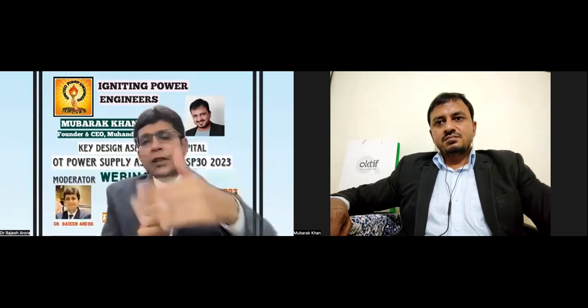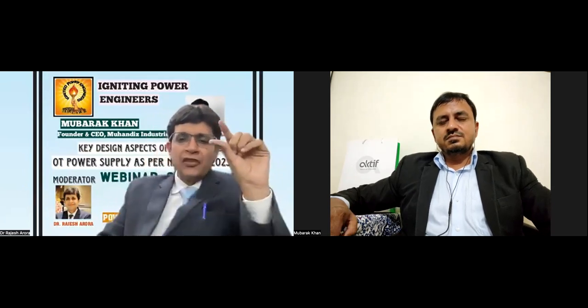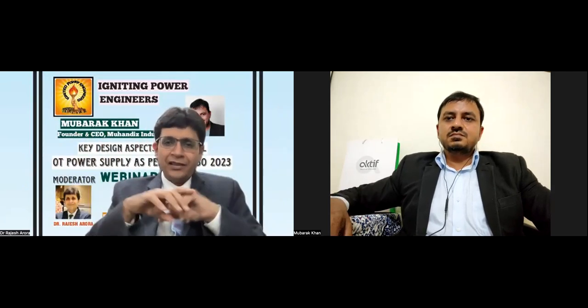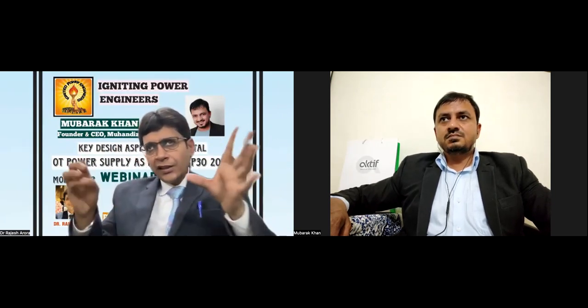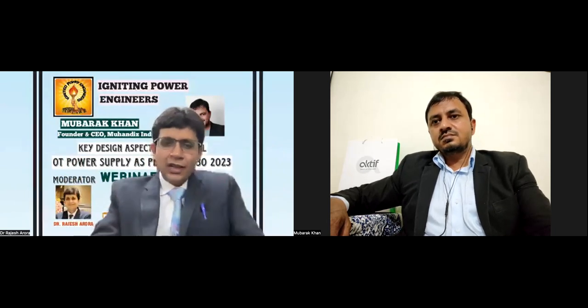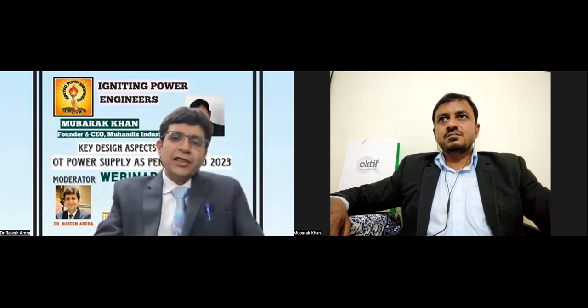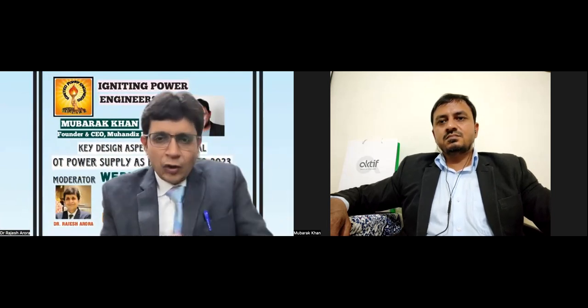If there's some problem with any of the feeders, the insulation monitoring system gives an indication and an alarm. The alarms are in the shape of indication as well as sound, and they will not reset until they are attended by a person working in that hospital. That is the system of working. Your question was about the second phase coming in contact with earth. Usually we use a single phase transformer, as I have seen in the specification, and there is no second phase at all. Only a particular feeder will come in contact with ground, and that will be through the isolation transformer and monitored by the insulation monitoring device, if I'm not wrong.